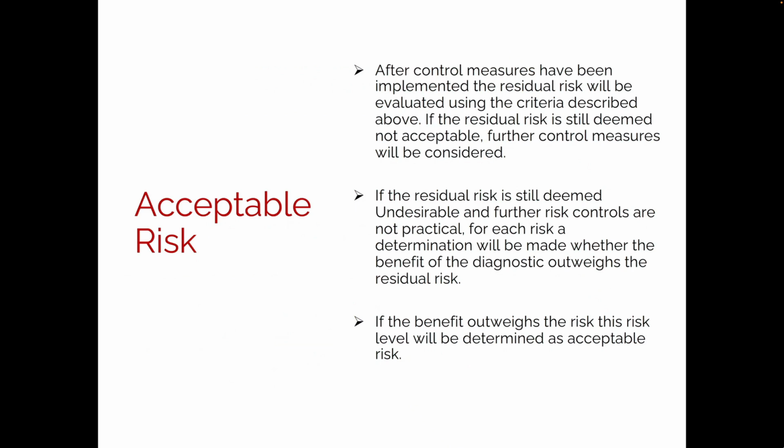So after the control measures are implemented, or you basically say, well, if this is the level of risk, and if I implemented this control measure, there's an assessment of what's the residual risk after you've implemented those, or you expect to implement those controls. And if that residual risk is fine and you're landing in a good zone, then you just have to document the risk, the benefit of the device outweighs the risk, and you don't have to do any more.